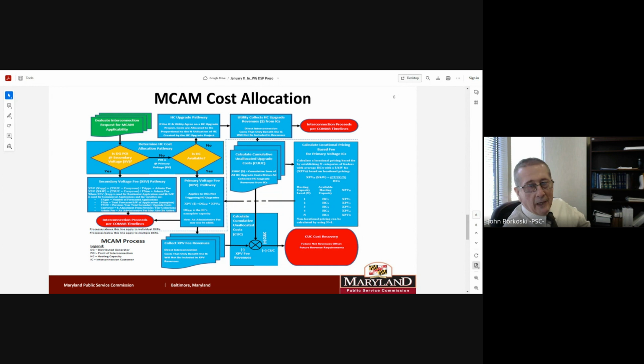So if you go from a 25 kVA transformer to a 50 kVA transformer, now you have the ability for all the homeowners also serviced from that transformer to interconnect and be a free rider. The first causer homeowner paid for the new service transformer, and then all the subsequent homeowners that wanted residential systems could interconnect using that capacity until you needed another upgrade. So we had a problem with both primary voltage interconnection and secondary voltage interconnection, with two different methodologies for cost allocation.